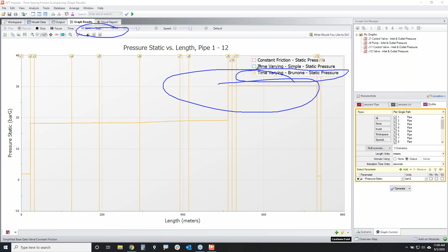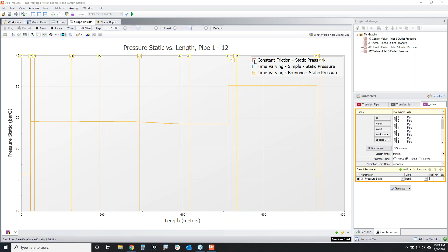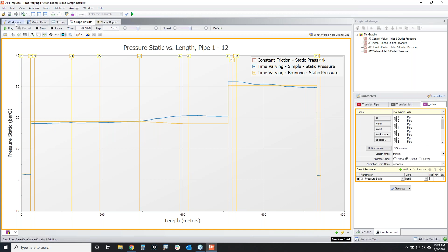So when you see that the blue and red lines are still changing significantly with those other friction models, constant and time varying, if I uncheck those and just play the yellow one, as you can see here, the time is changing but the values are not. So using the time varying Brunone equation for friction that's allowed to change, your system dampens out much faster than it would with using constant or time varying friction, which would be constant or the original variable resistance.